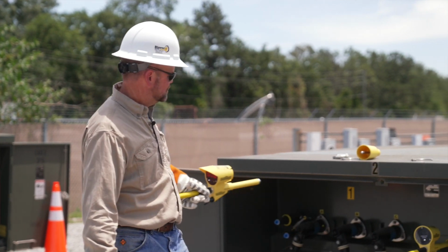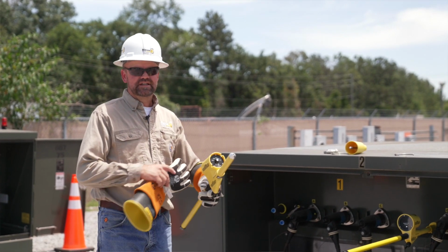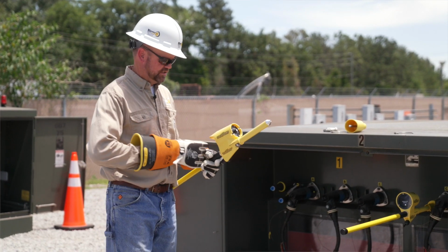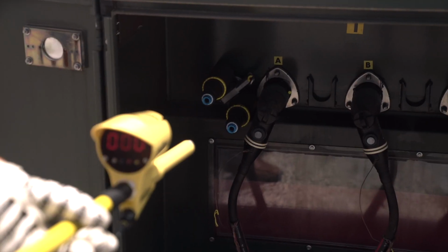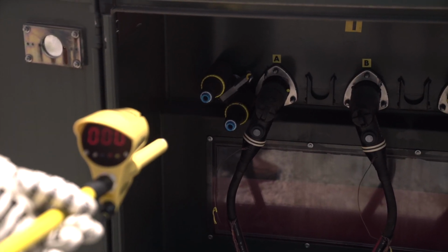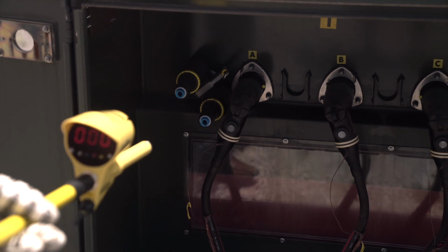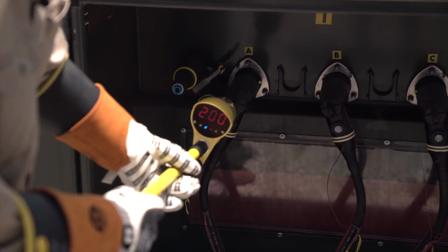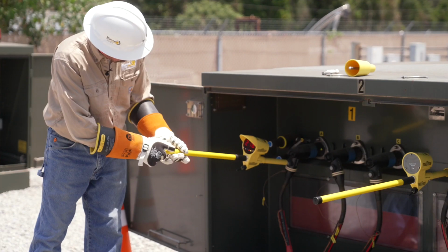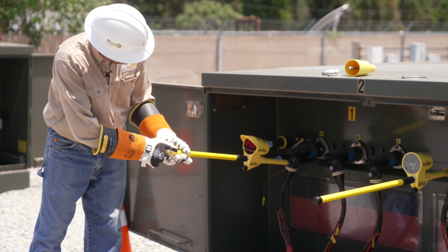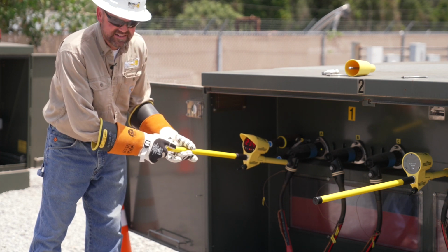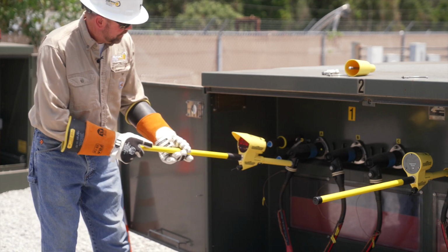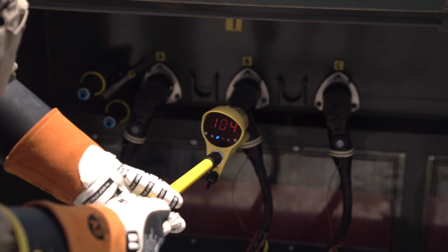I can go ahead and determine what phase is feeding that side of the switch. So again, you can touch any one of the three phases. It doesn't matter which one you start at. So I'll just start on the left side. I have my red light. It goes up near 240 degrees, so I know in fact this does not feed that primary bushing on the other side of the switch.